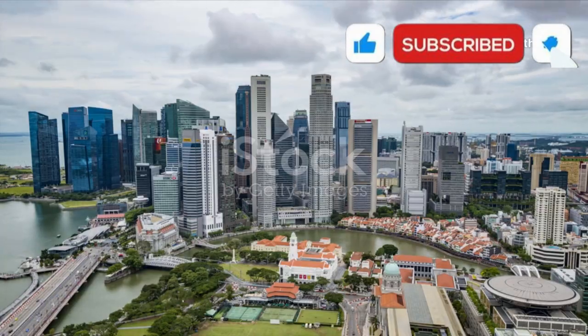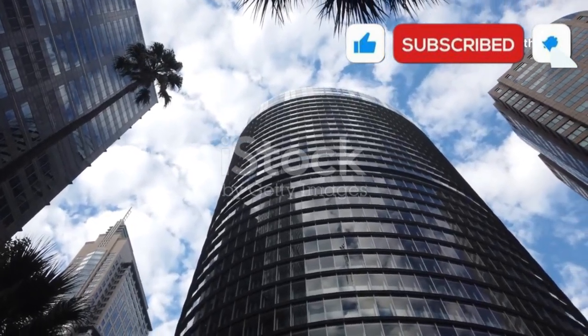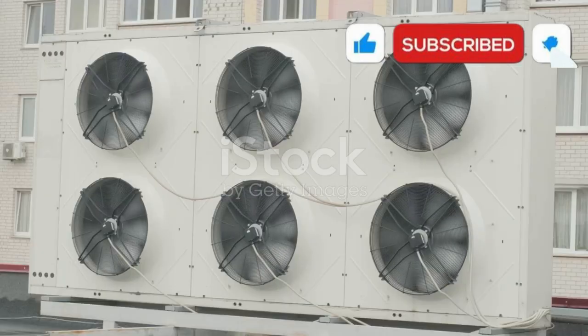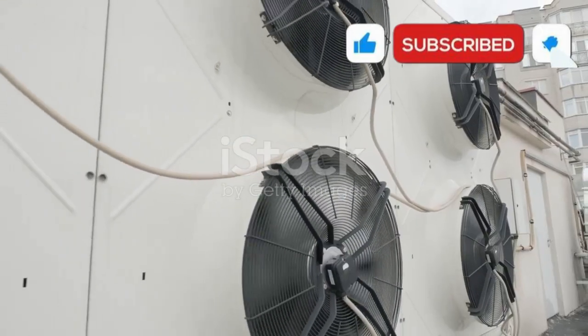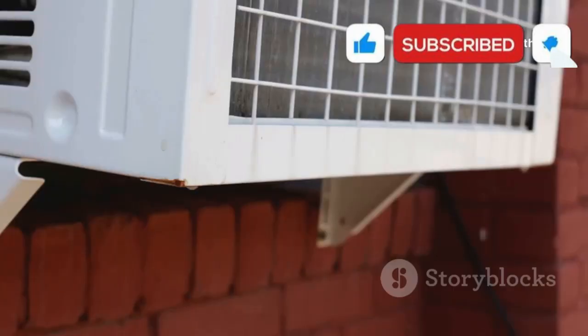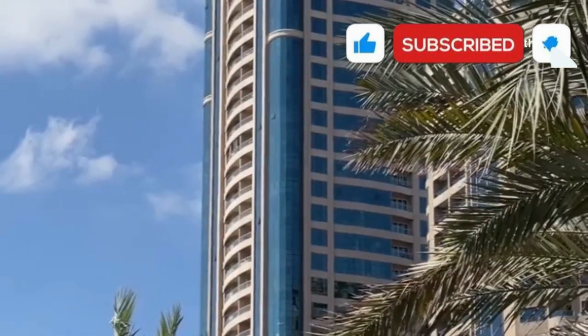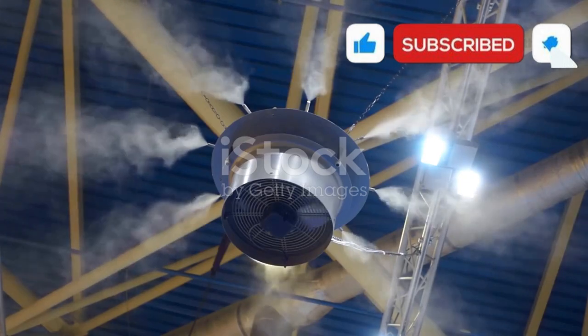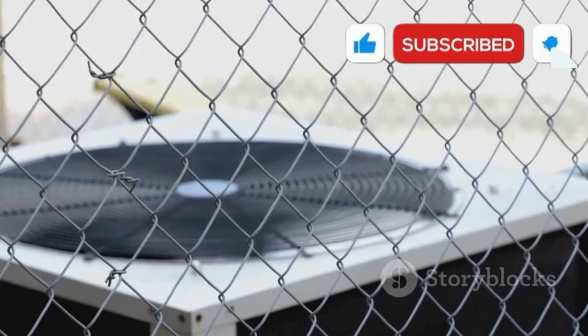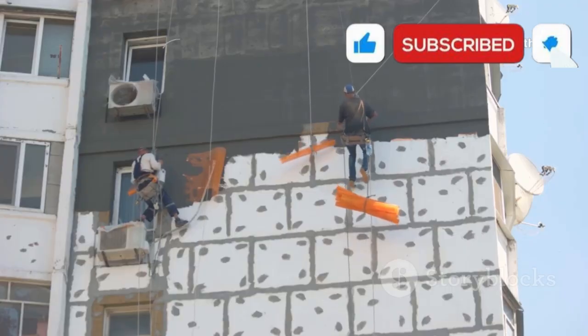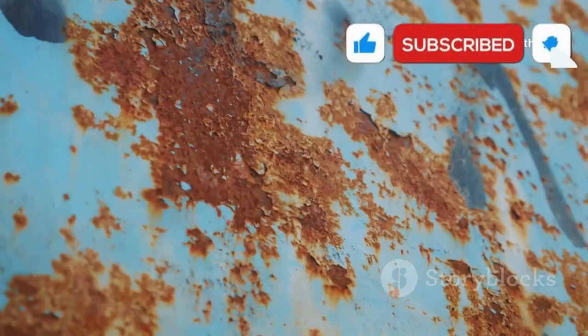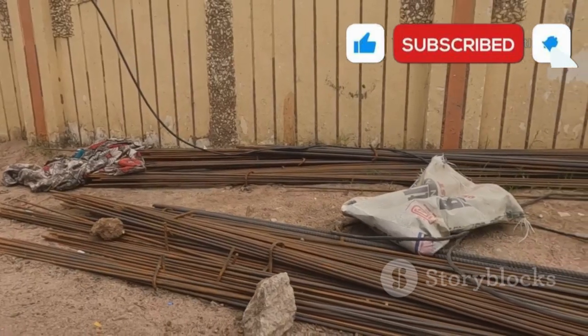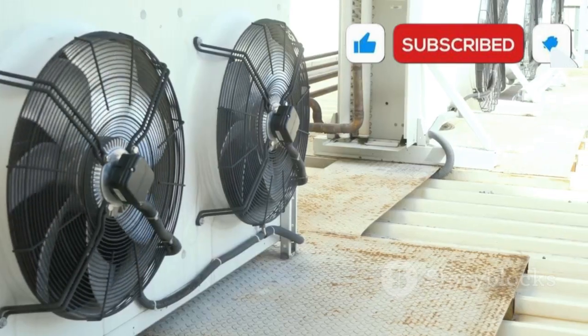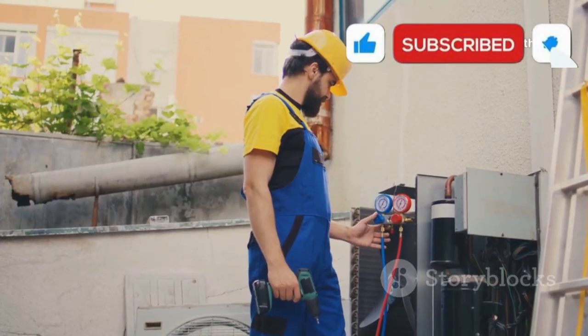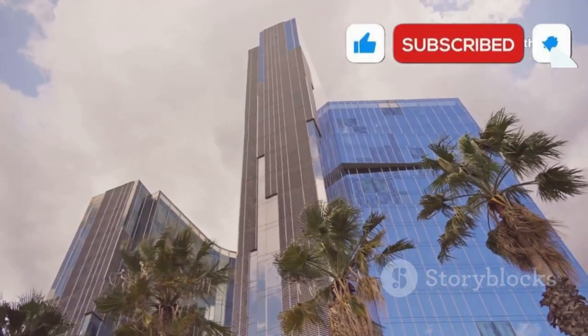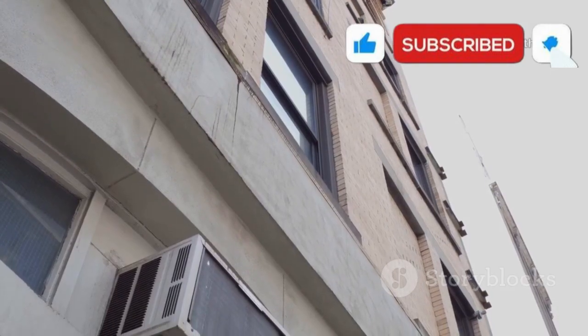In tropical cities like Singapore and Miami, skyscrapers face heat and relentless humidity. The challenge isn't just cooling the air, it's removing moisture to keep people comfortable. HVAC systems dehumidify by cooling air over cold coils, causing water vapor to condense and drain away. In extreme humidity, dedicated dehumidifiers or desiccant systems may be needed. Buildings like the Petronas Towers run their systems almost non-stop to fight heat and moisture. Engineers use insulation and vapor barriers to prevent condensation and mold. Corrosion is a constant threat, so materials must resist rust and decay. Air quality is a top priority. Fresh, filtered, dehumidified air is essential. Regular maintenance keeps everything running smoothly in these harsh conditions. Managing humidity is key to comfort and building longevity in the tropics.